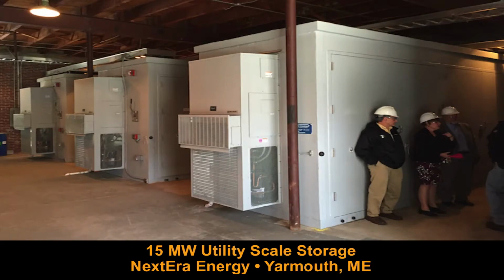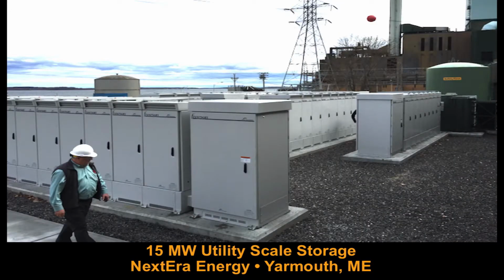Stepping up to a larger, much larger installation: 15 megawatts of utility scale storage at NextEra's peaker plant in Yarmouth, Maine. They put the batteries inside because this is Maine, and lithium ion especially is sensitive to cold and doesn't perform as well, so it's in a climate-conditioned area with its own climate conditioning. The DC to AC inverters were put outside because they're happy to be cold—they run better that way. And they used a lot of small inverters because they were worried that if they had one or two big ones, they'd be prone to loss of power if those failed.